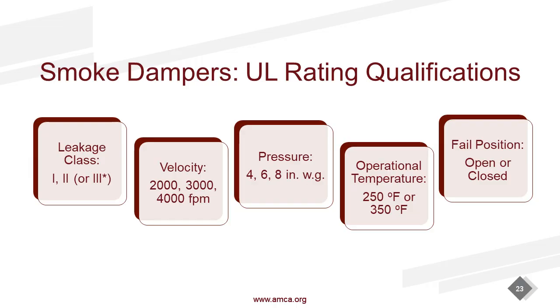It is very important. For dampers that are rated and shipped as fail closed, you cannot just simply flip the actuator over and call it fail open. That is a tested and certified rating. It has to be reflected on the label of the damper shipped from the factory. Otherwise you're going to have a damper that says it's fail closed and is actually failing open, and your building inspector should not allow that. So you must get that right at time of order.